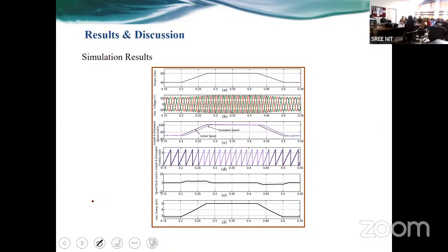That means if I have to maintain the voltage level simultaneously with the load current, the system must be operated below its capacity. Yeah, exactly. Otherwise, if you are utilizing over capacity, then there is no option. You don't have backup, you don't have sufficient generation. What will happen? That is a mismatch condition. PG is equal to PD. If it is not equal, mismatch will always happen in terms of voltage and frequency fluctuation. That's it. Very simple.